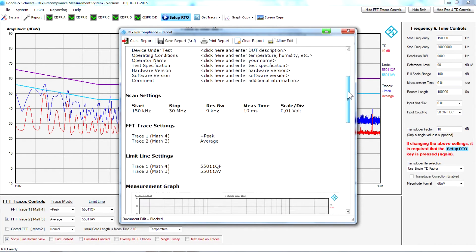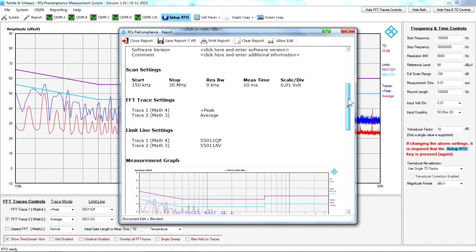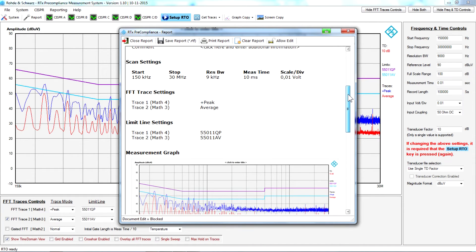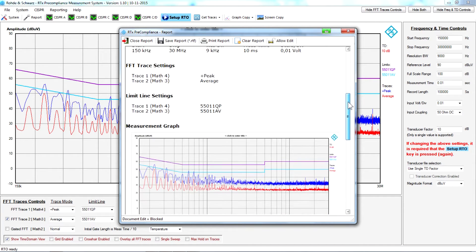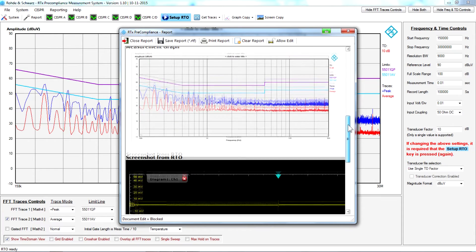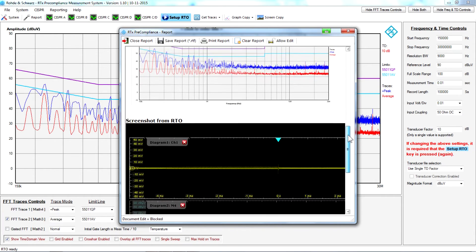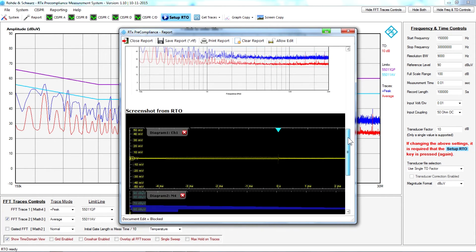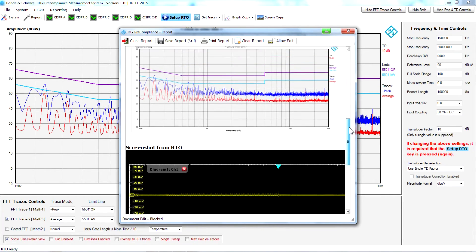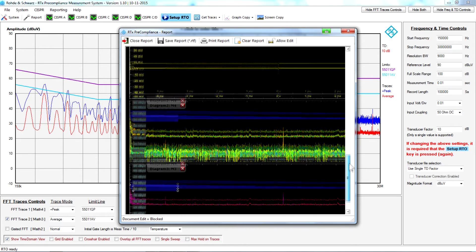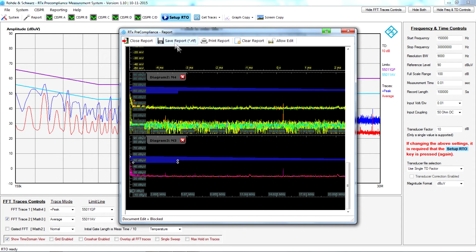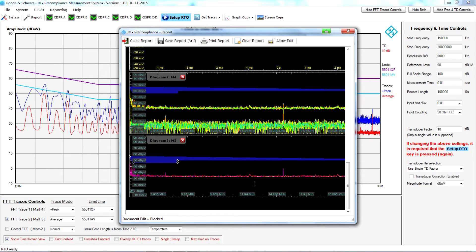You are getting all the settings for the measurement, what traces, what limit lines and so on you have been using. You have a screenshot of the actual graph from the software, and you can also choose to include the screen dump in the report. This can be saved to an RTF file and you can then later print the test report.